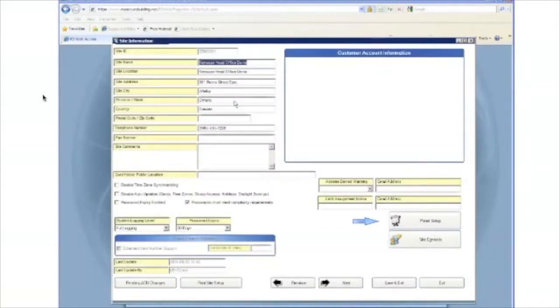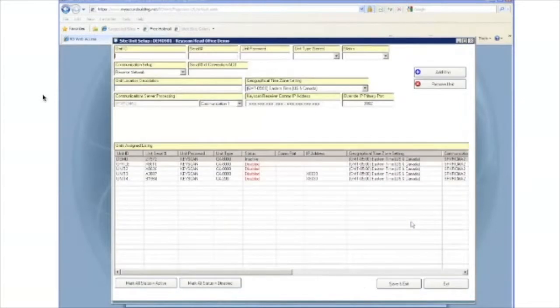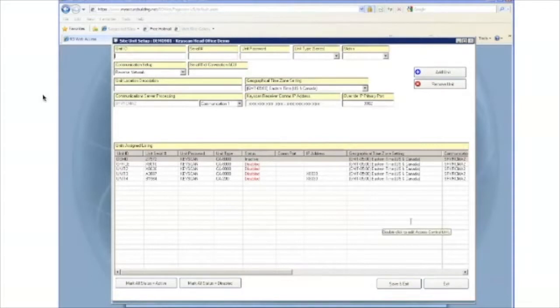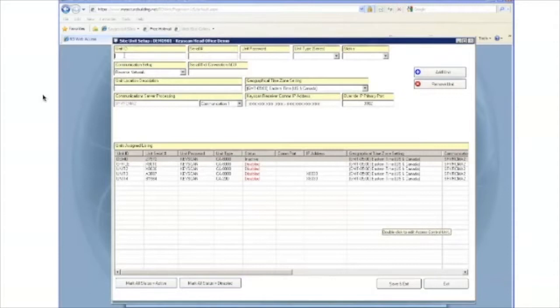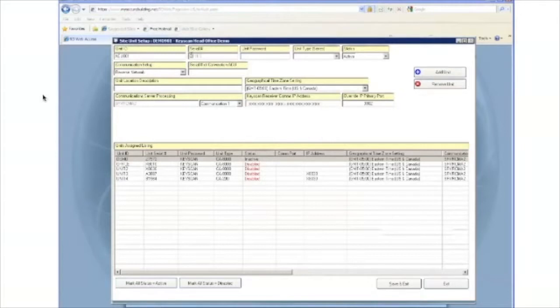Once in the site information page, go to the bottom right corner of that screen and click on panel setup. Now that we're in panel setup, we can go ahead and add our CA-150 control unit. To start, you will need to enter the unit ID. I will use a Keyscan default of ACU001. Next, enter your serial number of the CA-150. Enter the default password, which will be Keyscan all capital letters.